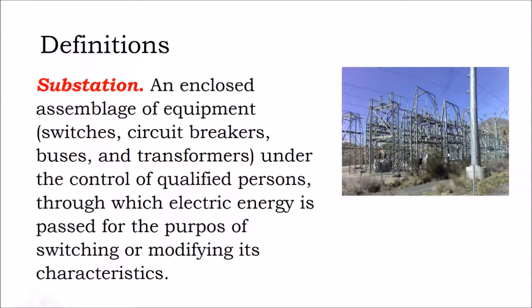Substation: an enclosed assemblage of equipment, switches, circuit breakers, buses, and transformers under the control of qualified persons through which electric energy is passed for the purpose of switching or modifying its characteristics. Substations will take your high voltage lines that are coming from the power plant and then convert that into medium voltage that'll go out to your communities. And then there'll be another medium voltage conversion that'll step it down to your distribution circuits, and then another transformer conversion that steps it down to your power lines that come into your home, which are your 240 volt split phase or 208 three phase or 208 delta, 208Y.